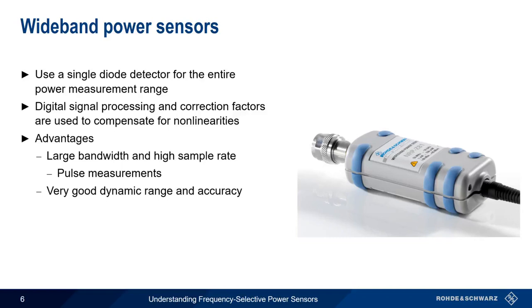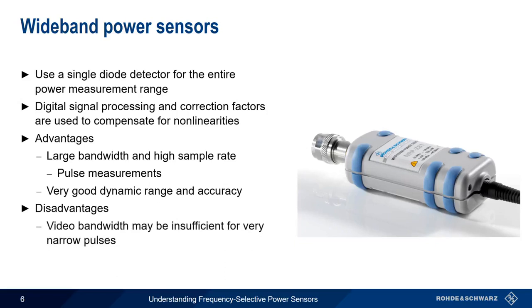Even with this wider bandwidth, a potential disadvantage of wideband power sensors is that their video bandwidth may still be insufficient for measuring very narrow pulses.